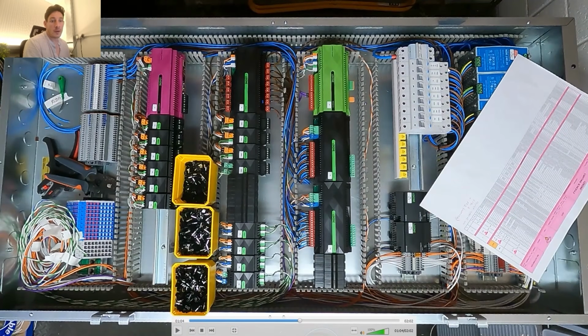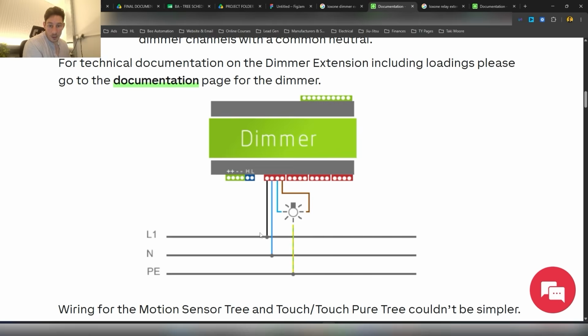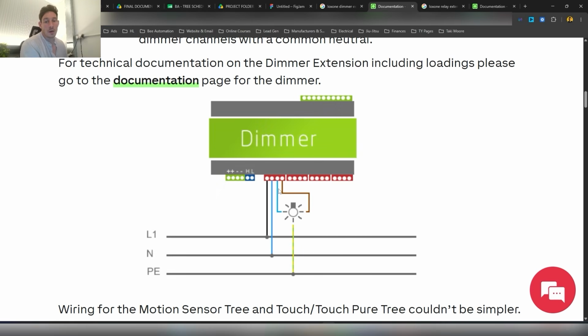Because our neutral from the RCBO is already coming in on the feed side, we're not taking that to the terminal block. Let me show you what we've just done. We already had our feed and our neutral going in, and now, imagining there's terminal blocks here, we've wired the dimmed output side for both the neutral and the live into those terminal blocks. Then, out in the field, on the other side of the terminal blocks is where we'll put our cables to the light.